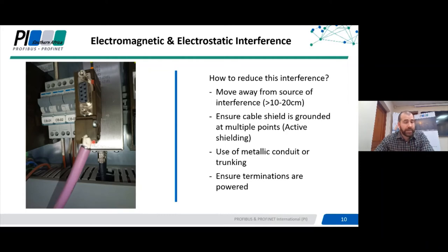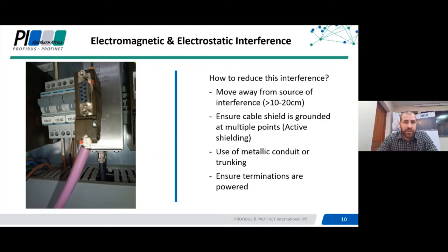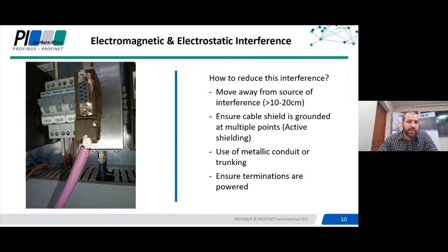This is an example of a cable where the shield has been terminated short, probably because a Stanley knife rather than a proper tool was used to strip the cable. This is a very big problem because any electrostatic or electromagnetic interference picked up on this cable will travel down the cable and has no path to ground, and will end up affecting the cores inside the cable.